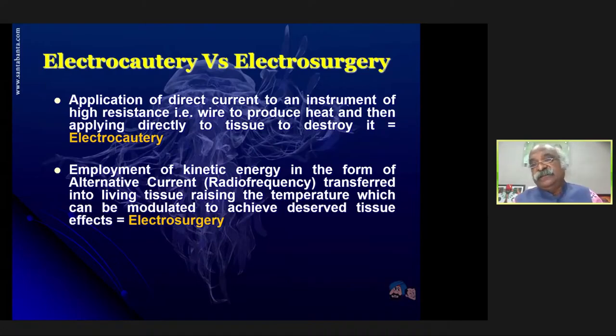That's known as electrosurgery. So one thing is that it's kinetic energy, an alternating current, a radio frequency current, which is generated from the electrosurgical device and transferred to the tissues, and that can be modulated. The electrosurgical device is designed such that you can modulate the type of current, the power setting, the voltage, the current strength, everything can be modulated, and that modulation has a different effect on the tissue. That's known as electrosurgery.